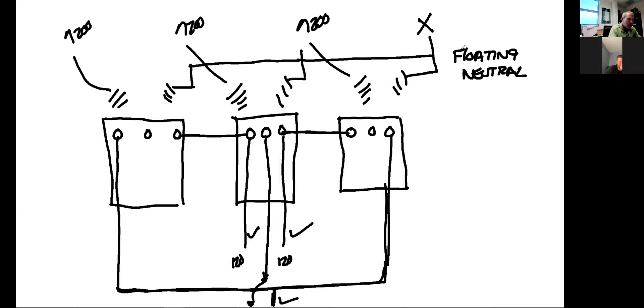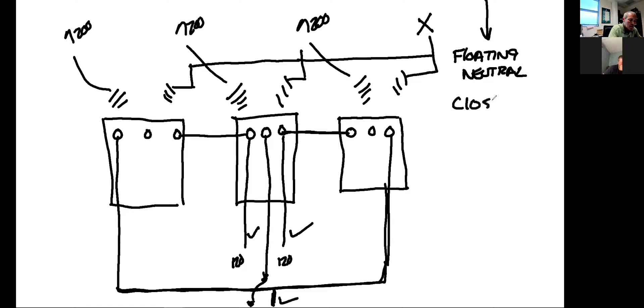As soon as you take the left-hand transformer away on a closed delta bank, you've now got an open delta bank. You just created that real quick and easy. The thing that's different is closed delta is the only bank that has a floating neutral. All others are tied into ground.